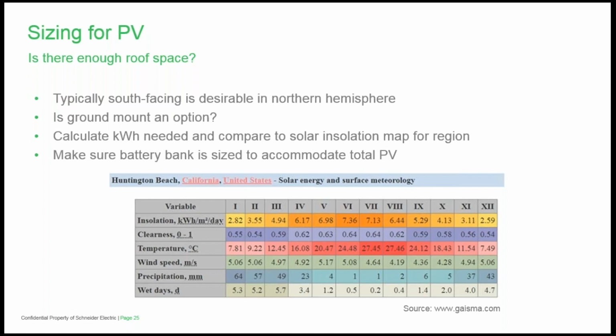Calculate the kilowatt hours that you're going to need, compare it to a solar insolation map for the region that the system is going to be located. And of course, make sure the battery bank is sized to accommodate a total PV. Here you can see an example of a solar insolation map for Huntington Beach. Well, I lived there for a few years. Now I'm in the Seattle area, and the insolation here is less than half in the winter months, and it's maybe 80% of what you see here in the summer months.